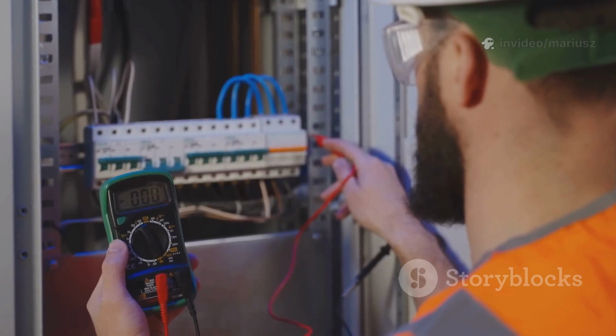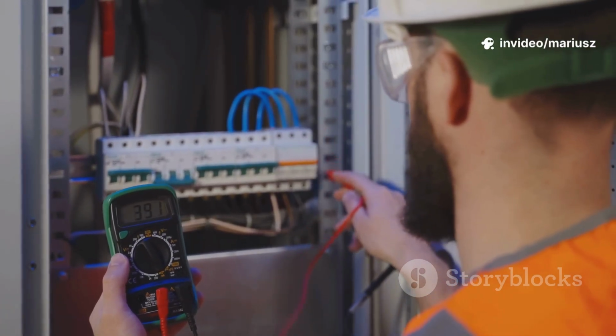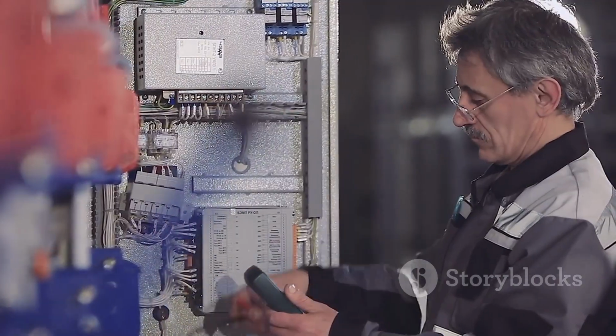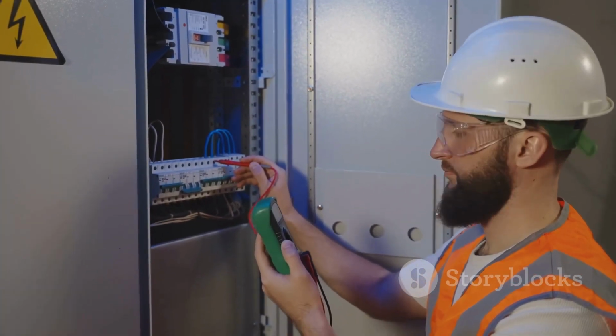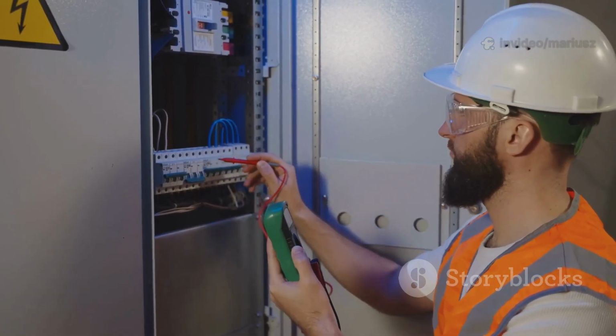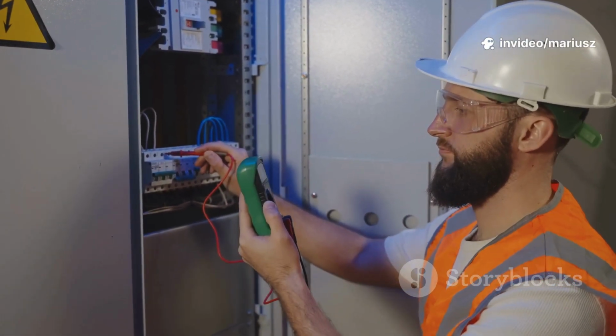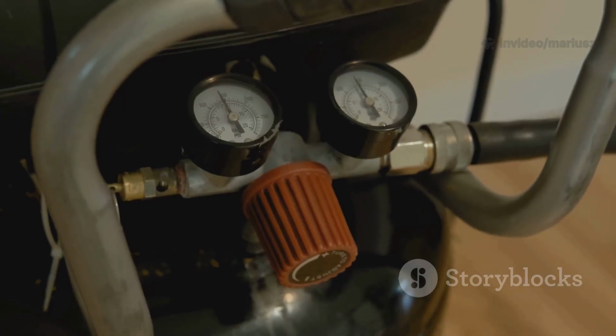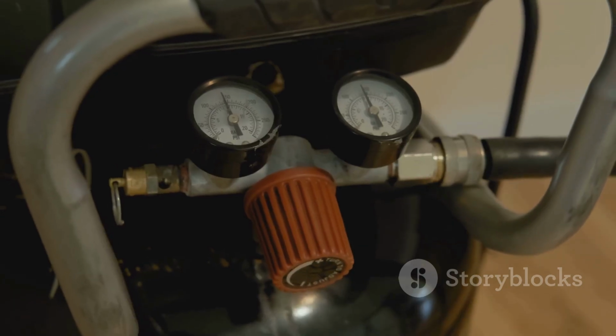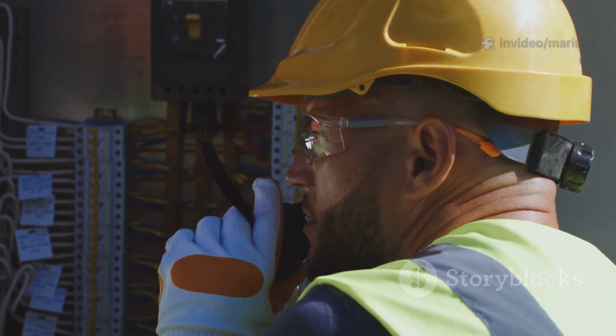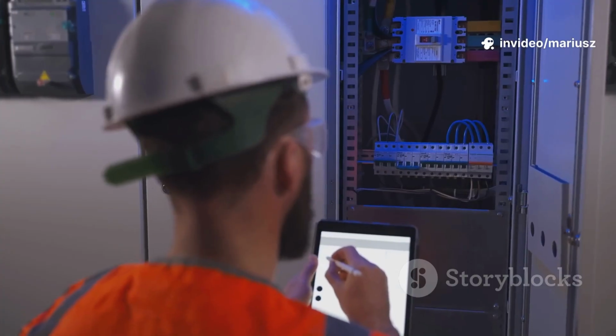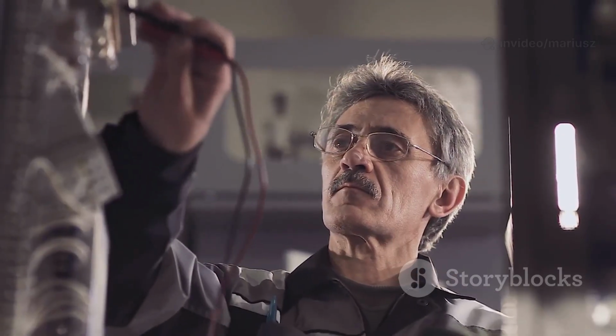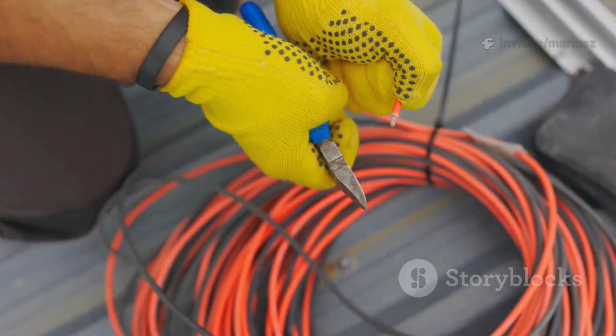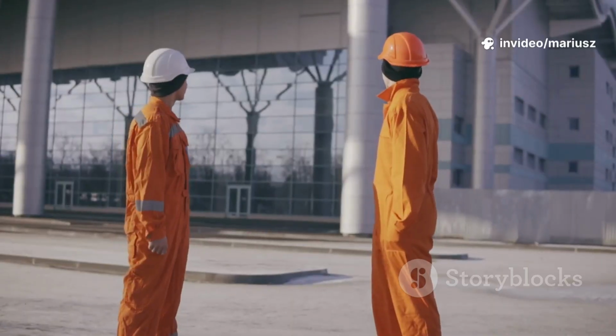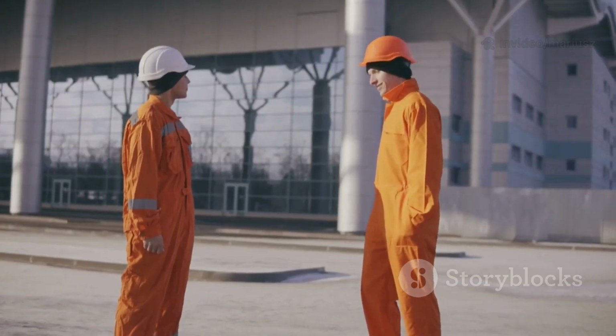The fourth, and arguably most critical stage, is to prove dead or devoid of hazard. This is our moment of truth. For an electrical system, even after isolation, the authorized person must use a tested and approved voltage indicator to physically test the conductors and prove there is zero voltage present. For a pressure system, they must check a calibrated pressure gauge to confirm it reads zero. This isn't about trusting the isolation, it's about verifying it. It's the final proof that the system is inert before any work begins. For electrical systems, this is immediately followed by earthing, where the conductors are connected to the main earthing system, providing a final fail-safe layer of protection. Only after these 5 stages are complete is the equipment considered safe to work on.